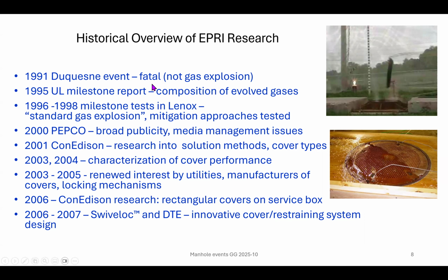Going one step back - I talked about gases exploding in uncontrolled explosions. What kind of gases are involved? EPRI sponsored a project at UL in Chicago to determine the composition of gases evolving from overheating cables. UL took many cables, overheated them in a controlled environment, captured the gases, and identified them: hydrogen, carbon monoxide, methane, ethylene, and acetylene.